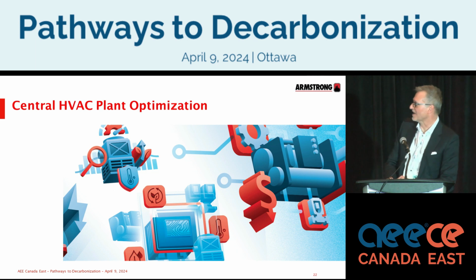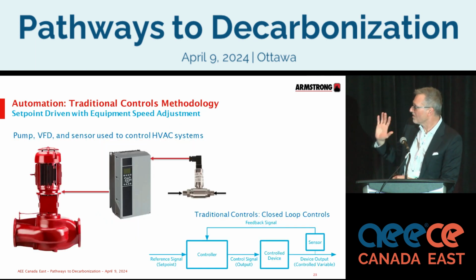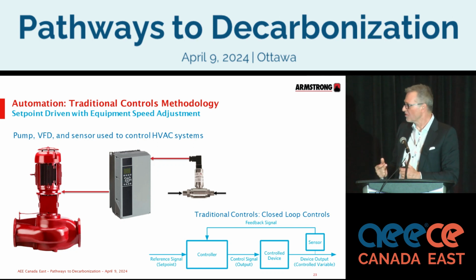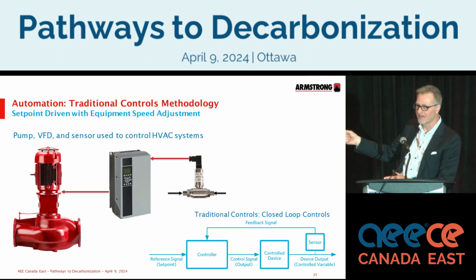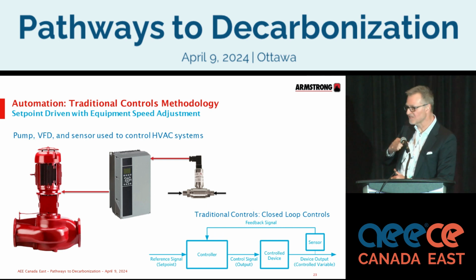So what is HVAC plant optimization? Well, if you look at the traditional scenario, what you have are PID loops in that setup. On the pump side, you have a DP sensor located somewhere remotely in the system. When a valve opens or closes, there is pressure on either side of that sensor, and there's a diaphragm in the middle. That diaphragm moves from its zero set point, and as a result, it sends a signal to the drive to either speed up or slow down the pump. The pump doesn't know what flow it has to give or what head it has to produce. All it knows is it either has to speed up or slow down to get to that set point. And then once it gets to that set point, you're back to a stable state.